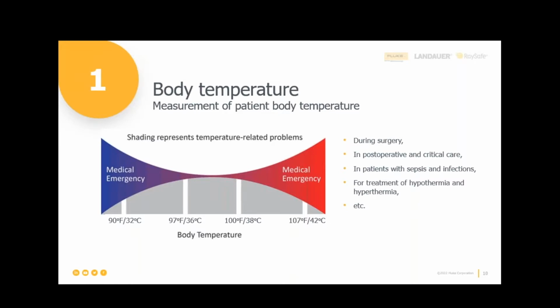So the accuracy requirement comes from there and it passes through the manufacturer of the medical device in their design validation, and ends up in the brand and model specific test procedure from the service manual of the device, in this case, the patient monitor. So we should expect to see the same accuracy requirements in that test procedure as we see in the standards, right?